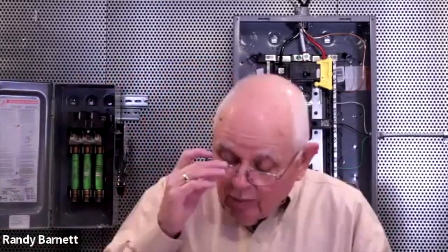But anyway, let's see what it has to say, it actually falls under enclosure interlocking and protecting people from electric shock. 6.2.3.2, number 3, says all live parts mounted on the inside of the doors that are operating at or above 50 volts RMS AC or 60 volts DC shall be protected from unintentional direct contact by the inherent design of the component or the application of barriers or obstacles, such that a 2-inch sphere cannot contact any live parts.